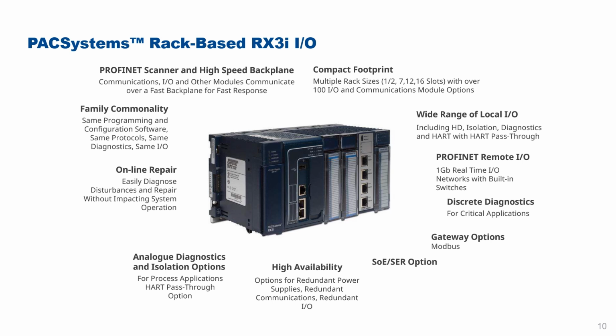We have a sequence of event recording option built into the firmware to allow time stamping of discrete signals down to 1 millisecond. And with the range of modules, we now have a choice of 1 or 2 racks, or 7, 12 or 16 slot racks, and again, the same 100 I/O and communication module options we had before. Options for I/O include high density, isolated I/O, advanced diagnostics, including HART pass-through, and all based on Profinet using 1 gigabit networks.